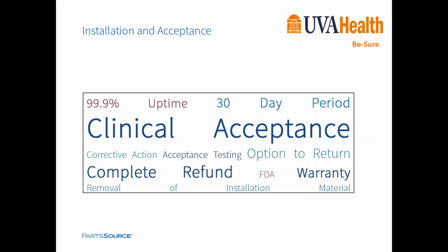All right, so we'll start with installation and acceptance. And I think the most important thing about this slide that I can tell you is that once you have accepted a piece of medical technology, the burden falls 100% on the organization receiving the technology if you are attempting to negotiate the return of that technology. So acceptance is a legal term, and in the vast majority of medical equipment contracts, acceptance is deemed, which means the vendor has terms and conditions that would say upon installation or upon first use, the equipment is deemed to be accepted, and that legally starts the warranty period.